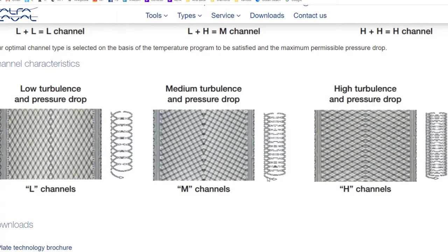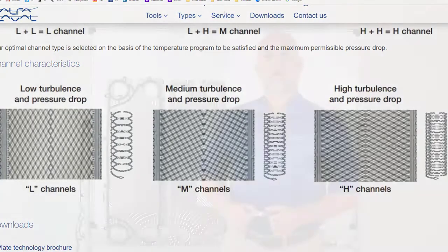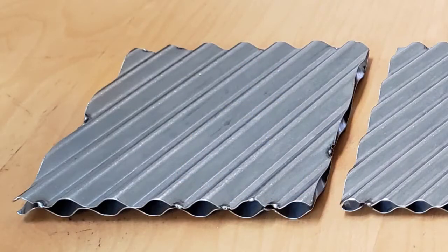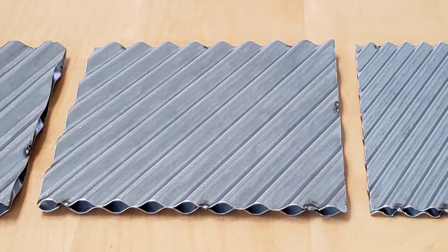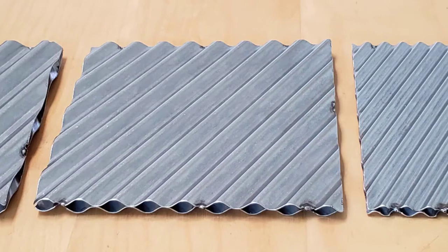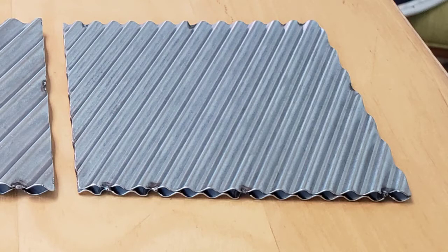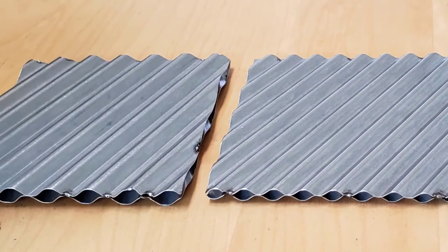Finding the right design for your application is more complex than just high theta and low theta. Another key aspect is the pressing depth. Alfa Laval generally has three pressing depths depending on the size and the model. The pressing depth influences the size of the channels, which in turn determines what kind and size of particles can pass through the heat exchanger. This has a significant impact on the fouling rate, but it also impacts the design itself. Smaller pressing depths guarantee a higher shear stress. If you do not have large particles in your fluid, it is always preferable to use the smallest pressing depth, since a higher shear stress gives the unit more fouling resistance. Fluids with a higher number of large particles would need a larger pressing depth. You have to balance the pressing depth by understanding what kind of shear stress you can achieve with the size of the particles in your fluid.